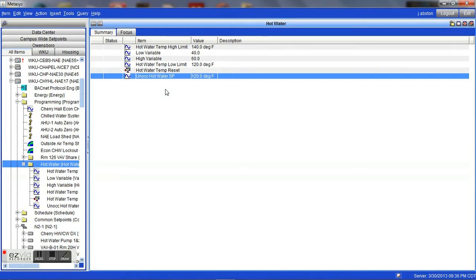The first thing that we do here is create a hot water temp high limit. This is going to be the maximum temperature that our system is going to be allowed to calculate to. The hot water temp low limit is going to be the lowest temperature that we're going to allow the system to calculate to. We're also going to create an unoccupied hot water supply temp set point. When our air handlers and VAV system is unoccupied, it is not necessary to maintain a high water temperature — simply to have hot water waiting to be used. By lowering that temperature we can drastically reduce the utility usage.